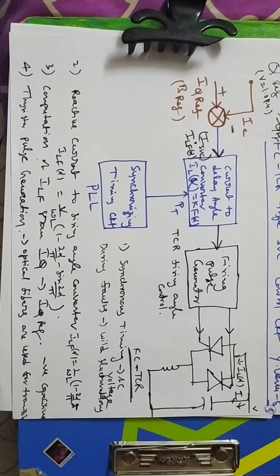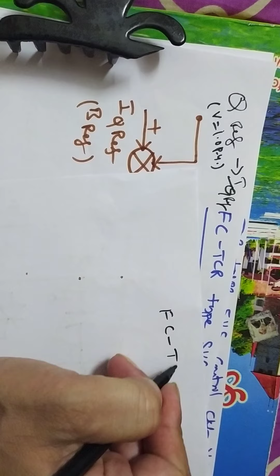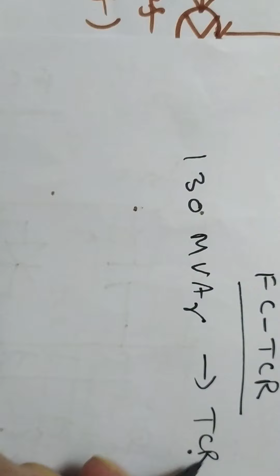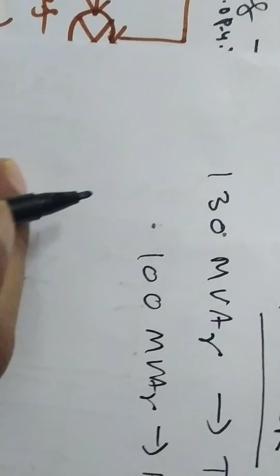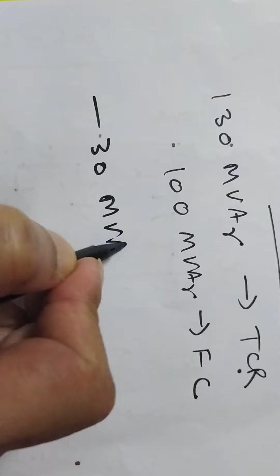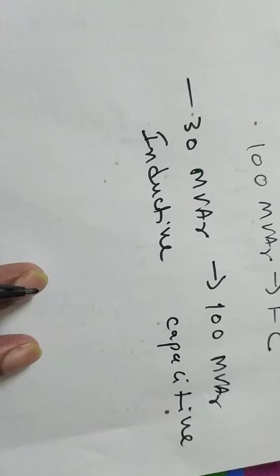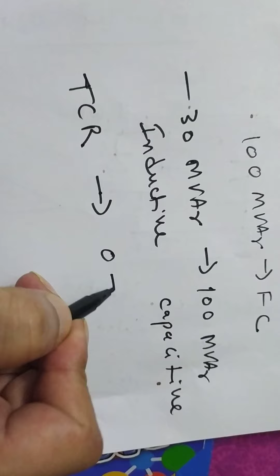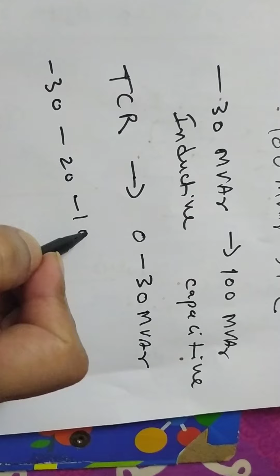Here again, this TCR will become bulky, approximately 130 MVAR. So in general, an FC-TCR type SVC has 130 MVAR of TCR rating and 100 MVAR of fixed capacitor rating. In which you can obtain from minus 30 MVAR to 100 MVAR. So this is capacitive, this is inductive. It is possible. In the inductive region also, TCR firing is valid from 0 to 30 MVAR. Therefore minus 30, minus 20, minus 10, plus 10, plus 20, like that you can control up to 100 MVAR.